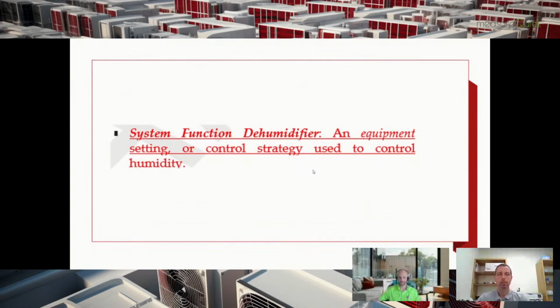I'm not a fan of this strategy. I know that it can be used as a poor man's dehumidifier, quote unquote, and it actually can work if you're using it in conjunction, in some climate zones, with an HVAC strategy that only provides extra dehumidification when the system is not doing it. But you have to be real careful about the amount of energy that you're using with this, because you can blow the efficiency of a piece of equipment out of the water by using this strategy.